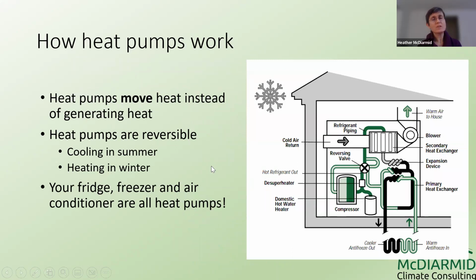One of the reasons I'm so excited about heat pumps is that they can be so much more efficient than all their competitors. A furnace can't generate more heat energy than the energy contained in the fuel, so its maximum theoretical efficiency is 100%. But heat pumps don't burn fuel, they use energy to move heat energy, so they can move more heat energy than the energy used to do that movement. A ground source heat pump, for example, can achieve 300 to 500% efficiency, meaning 1 unit of electrical energy can move 3 to 5 units of heat energy.